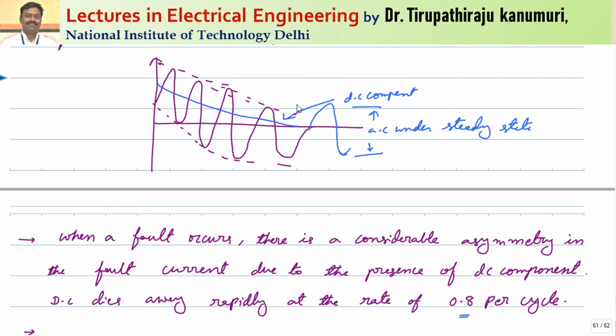Now coming to the instantaneous relays, because instantaneous relays operate at a very fast rate, they will operate within 1 to 2 cycles of your original signal. So that's why it will measure the total current, which will be the sum of the transient component, that means the DC component, and the AC component. So the total value of the current will be measured.